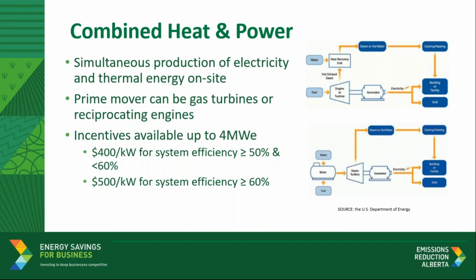Sure. Hi, everybody. So combined heat and power is also known as cogeneration. It produces electricity and thermal energy on site at the same time. The thermal energy that would otherwise be wasted is usually recovered to heat water, produce steam, for example, which is then used for other processes within the facility. The electricity produced replaces a portion of the amount drawn from the local utility, typically the base load, thus lowering overall cost of energy and also achieving carbon emissions reduction.